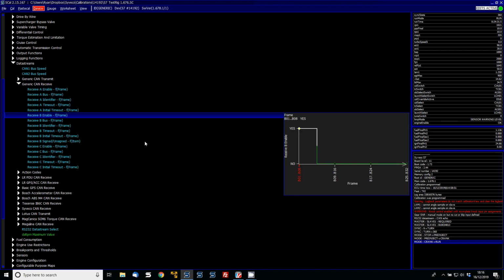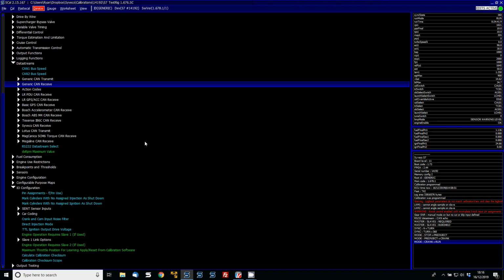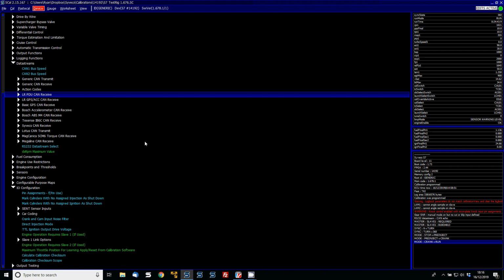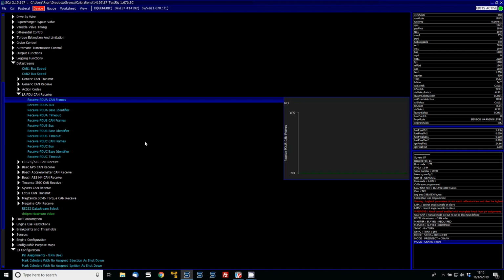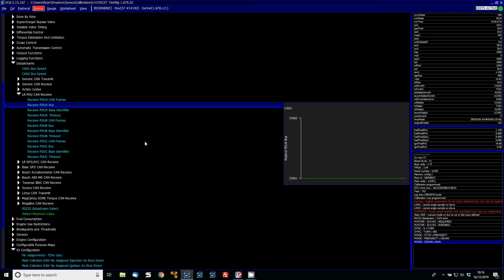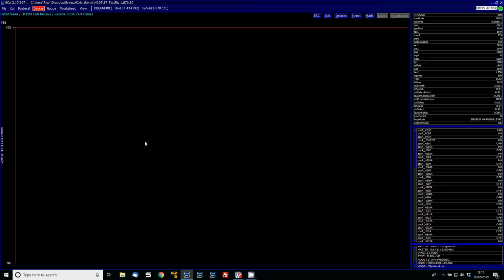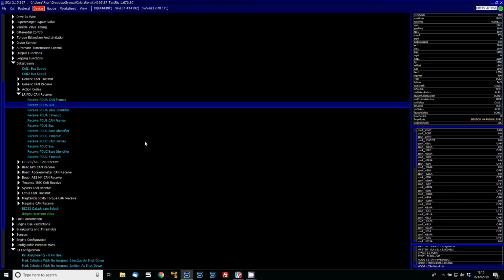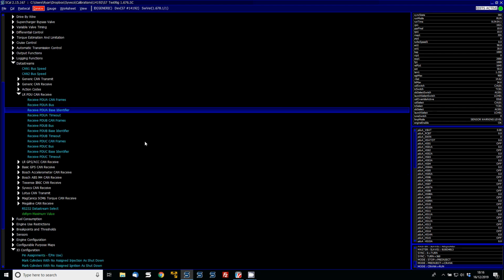The generic receive B, you've got up to 32 soft inputs theoretically that you can bring from the PDU into the ECU. Once you've done that, another thing you can enable is the LR PDU CAN receive. When you set these to yes, you need to set the bus again, so set this to yes, then set the bus to CAN 2, and the base identifier.